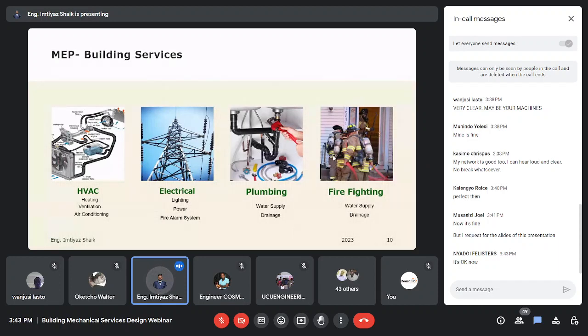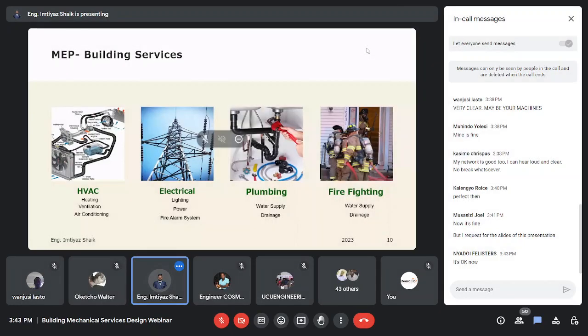We cannot say that in a 1,000 people sitting auditorium, you just put a few tube lights to get proper lighting. It doesn't work that way. You need to do calculations of lux, how much illumination you need to provide in the room, depending on the number of people, the area, the appliances used, and the type of room. It is very important for electrical designing in the building.